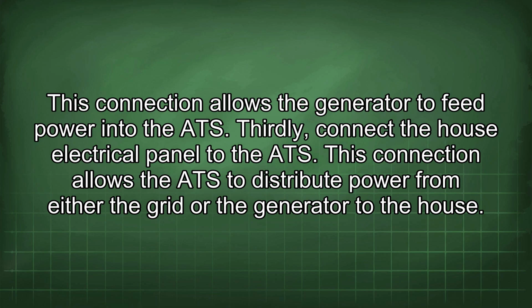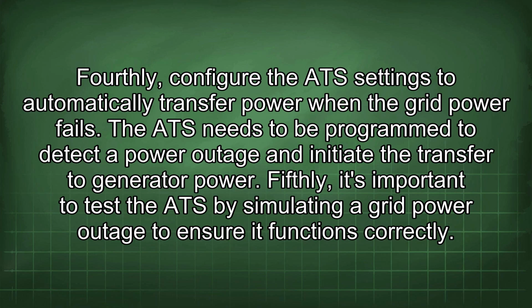Thirdly, connect the house electrical panel to the ATS. This connection allows the ATS to distribute power from either the grid or the generator to the house. Fourthly, configure the ATS settings to automatically transfer power when the grid power fails. The ATS needs to be programmed to detect a power outage and initiate the transfer to generator power.